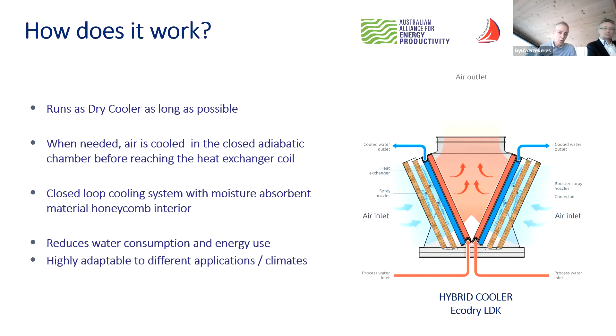If we compare the technology again from dry to hybrid versus wet cooling or a cooling tower, we can see several references. Taking the cooling tower as reference, moving from dry to hybrid configurations, we're able to get closer and closer to the wet bulb temperature, the typical reference for a cooling tower. The more we move from left to right using this technology, the closer we get. As a consequence, your footprint is reduced from dry to wet.